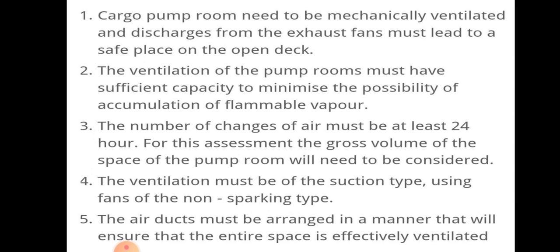Ventilation must be of suction type using fans of the non-sparking type. Air ducts must be arranged in a manner that will ensure that the entire space is effectively ventilated.